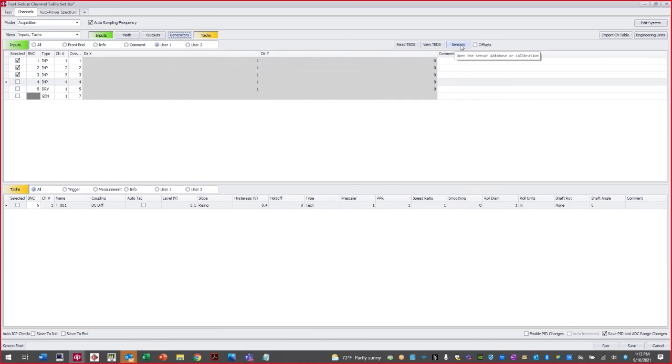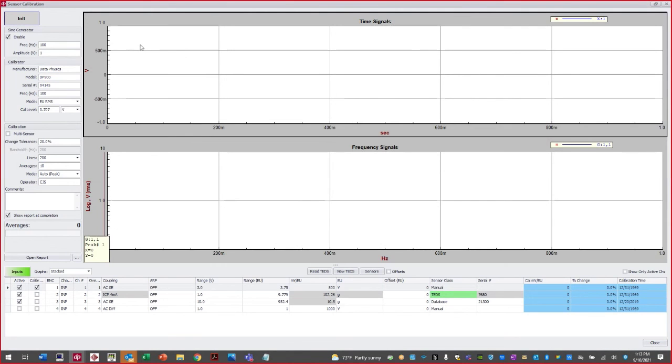The last thing I wanted to cover in detail today is our sensor calibration. This is a pretty neat feature of the software. There's a whole calibration panel. For right now, I have my source right into an input channel. I'm just going to calibrate on voltage.